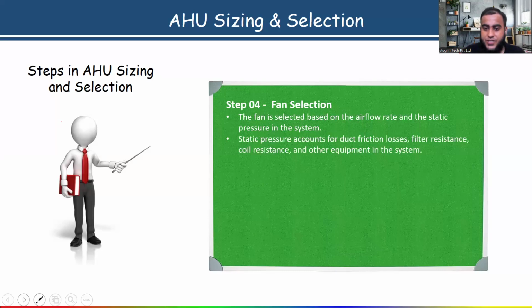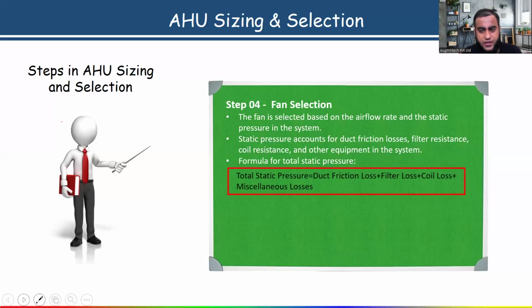Static pressure accounts for duct friction losses, filter resistance, coil resistance, and other equipment in the system. Is it clear? Formula for total static pressure: you have to calculate the duct friction loss plus filter loss, coil loss, and some other miscellaneous losses. The filter and coil losses will be given by the manufacturer. Our main target is to calculate the duct friction loss, and for that we have a separate calculation.